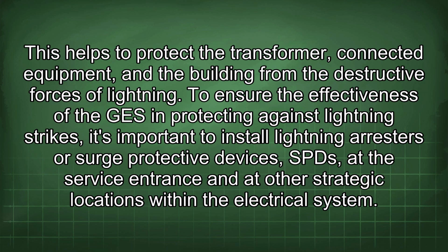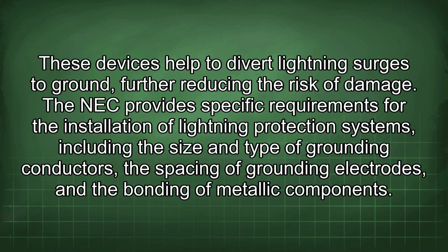To ensure the effectiveness of the GES in protecting against lightning strikes, it's important to install lightning arresters or surge protective devices, SPDs, at the service entrance and at other strategic locations within the electrical system. These devices help to divert lightning surges to ground, further reducing the risk of damage. The NEC provides specific requirements for the installation of lightning protection systems, including the size and type of grounding conductors, the spacing of grounding electrodes, and the bonding of metallic components.